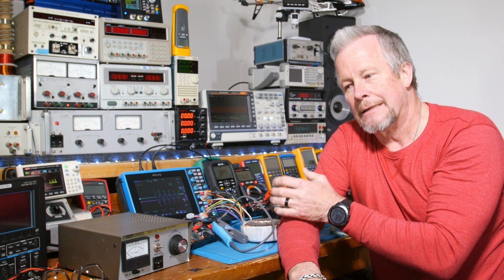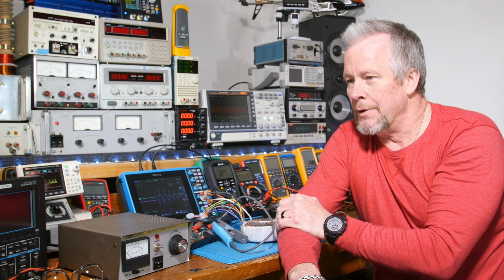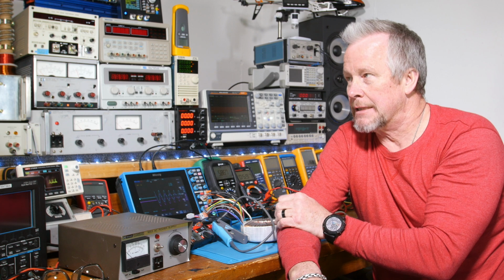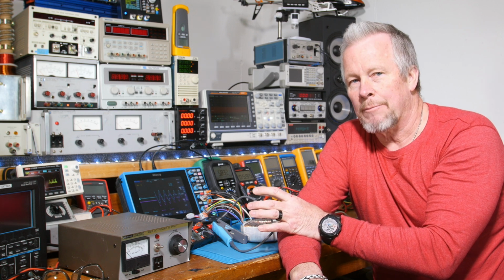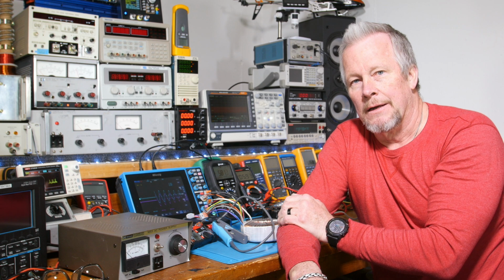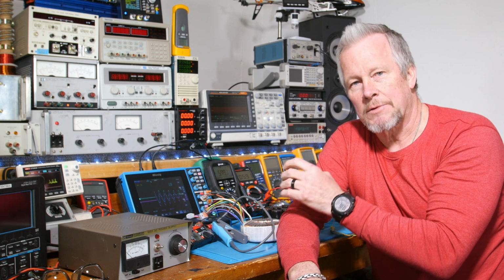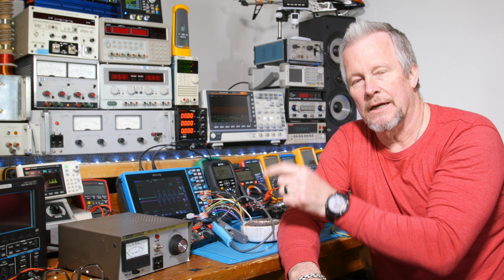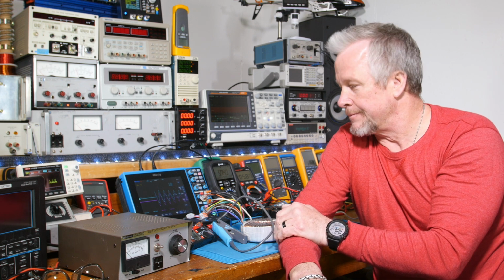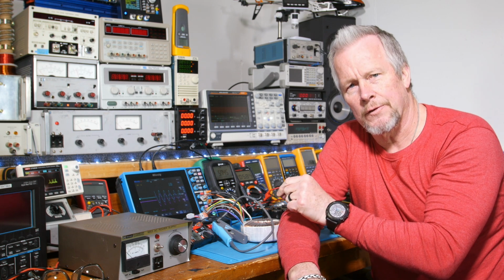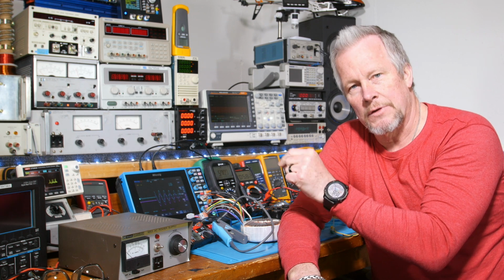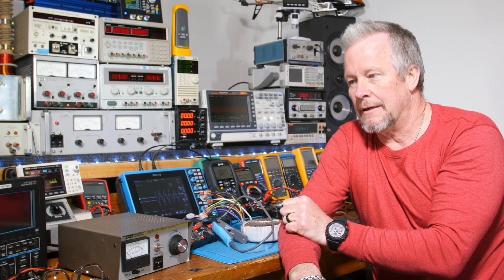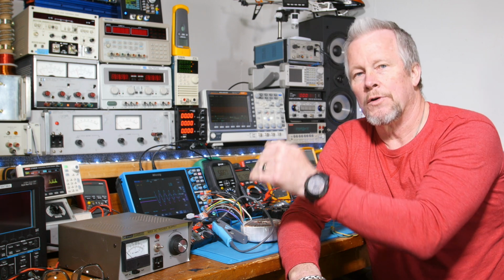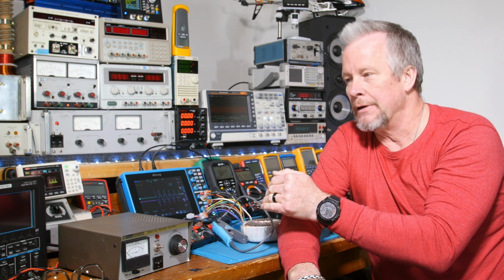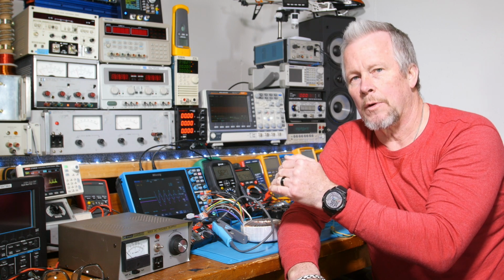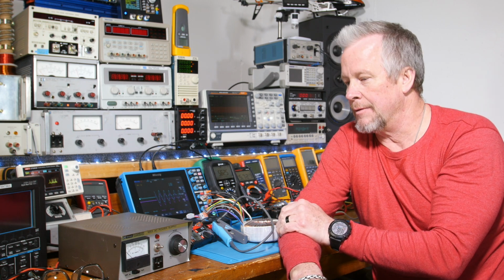That's a lot of the ways they're set up, and one of the reasons that makes sense is because circuit breakers, and even fuses, don't operate instantly. There's some time, there's an I squared T curve, and it has to do with how much current versus time, and depending on how much over the rating you are, say a 15 amp breaker, you have to be over that 15 amps for some time for them to pop.